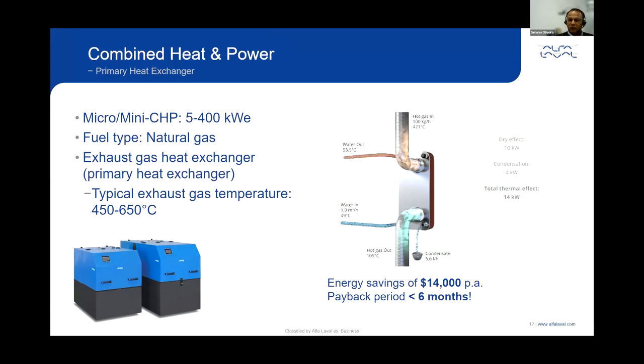This is an example of a combined heat and power unit where a primary heat exchanger to recover heat from engine exhaust gases was used. This particular duty recovered 14 kilowatts of energy, providing an energy savings of $14,000 per annum, using a conservative power consumption charge of 10 cents per kilowatt hour. So this resulted in a payback of less than 6 months.